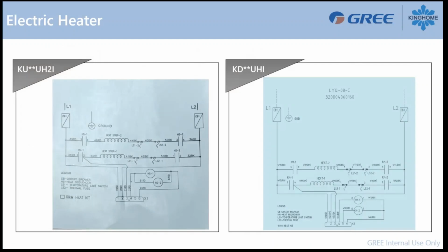If we take a look at the connection here, this is the schematic of the duct heater. So we have two different schematics. So I brought you here on the schematic this is a 10 kilowatt heat strip for both of them. So for the KU family, this is the schematic for a 10 kilowatt. And the KD family, you have another 10 kilowatt here with the schematic also. So basically a 10 kilowatt only using one breaker. So you will have circuit breaker 1 only.